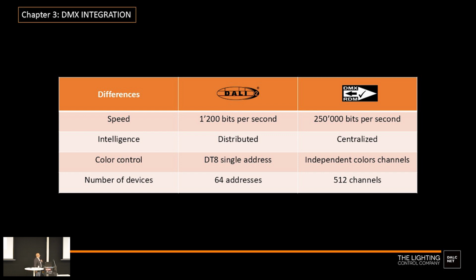Again, color control: in DMX we only have channels, not colors. So an RGB luminaire in DMX uses 3 channels, R, G, and B. In DALI DT8, an RGB luminaire is one address. So it's not easy to have a direct correspondence between a DALI address and a DMX channel. And of course the number of devices is completely different, so especially for big installations, having only 64 addresses can be a limiting factor for a DALI-only system.